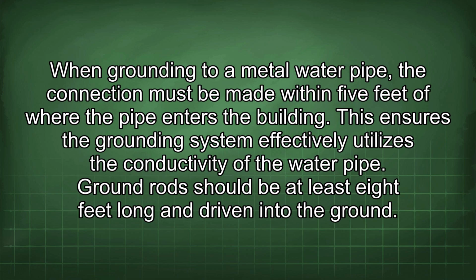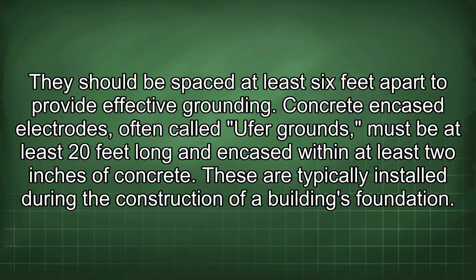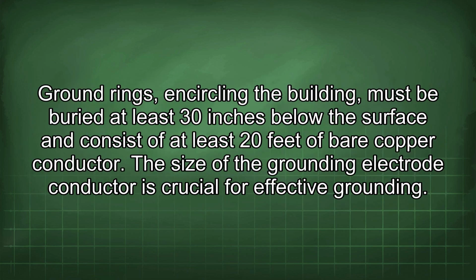Ground rods should be at least 8 feet long and driven into the ground. They should be spaced at least 6 feet apart to provide effective grounding. Concrete encased electrodes, often called UFER grounds, must be at least 20 feet long and encased within at least 2 inches of concrete. These are typically installed during the construction of a building's foundation. Ground rings encircling the building must be buried at least 30 inches below the surface and consist of at least 20 feet of bare copper conductor.